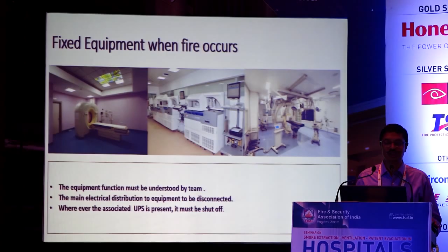There are some safety switches located with the equipment, especially fixed equipment. You need to ensure these are properly understood by the people. One point about the safety switch in the MRI, which is also shown: the safety switch can be used only when it is needed, when somebody is stuck. When you use that safety switch, the magnet loses power, it quenches. To ramp up the magnet again, you will have to spend at least 1 crore. So people have to know the significance of each of these safety switches, when they are to be used, and who has to use them.